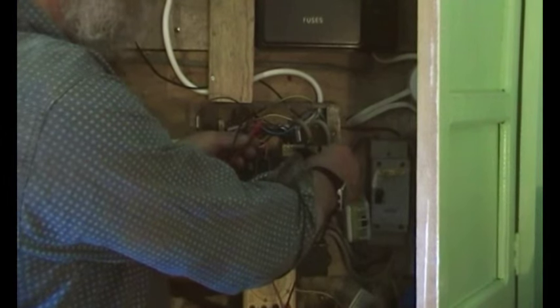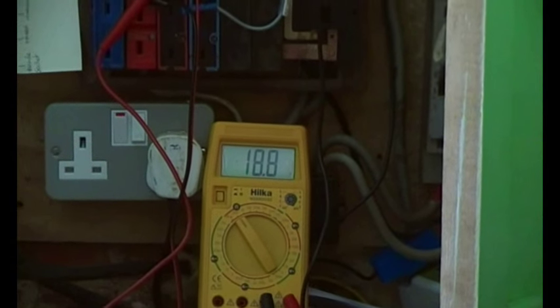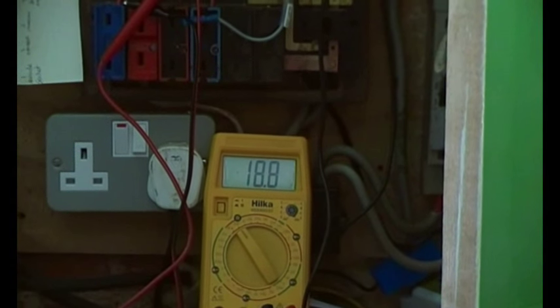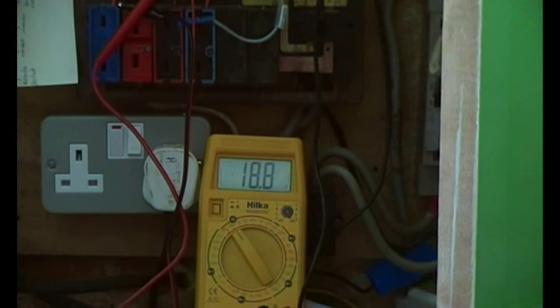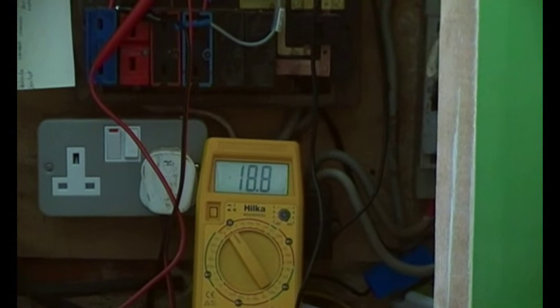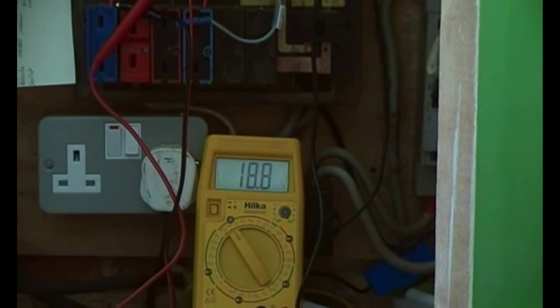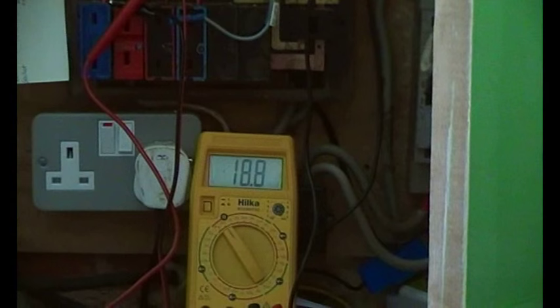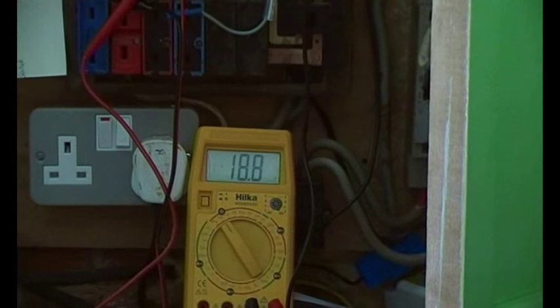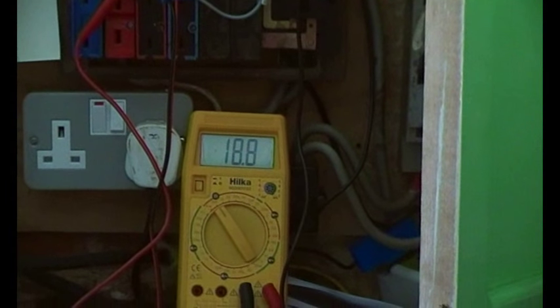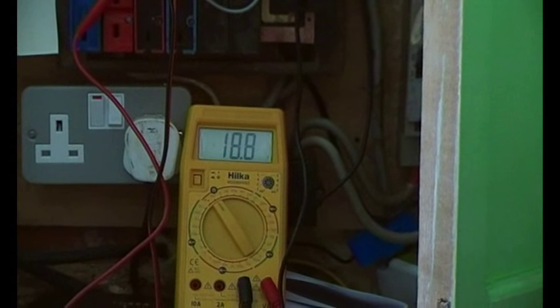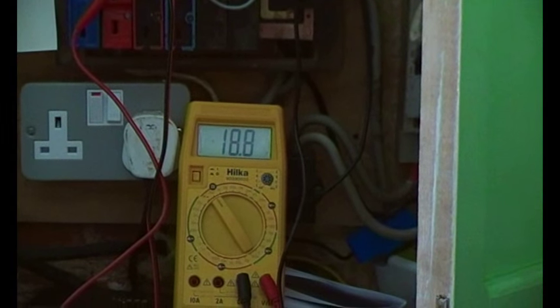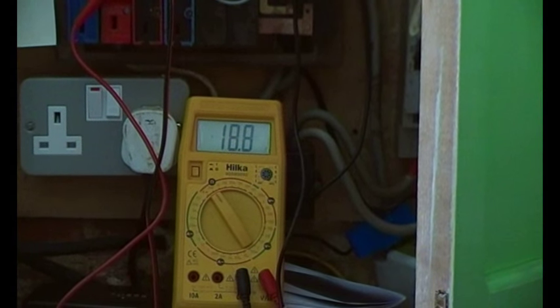Let's do it the right way around. So we've got there to the neutral. So there we go, 18.8. And that is the resistance, 18.8 ohms, that's the resistance of the immersion heater circuit. So that's within tolerance because I think the minimum was 17.